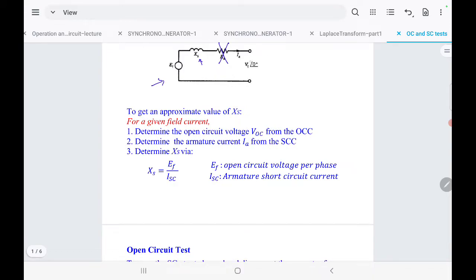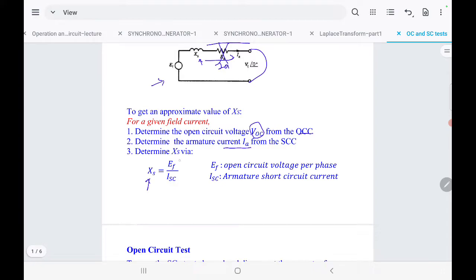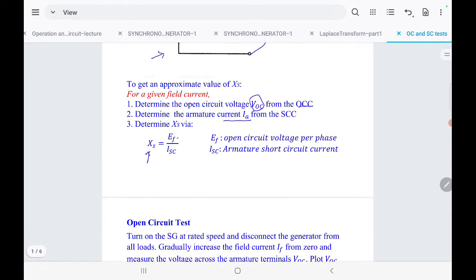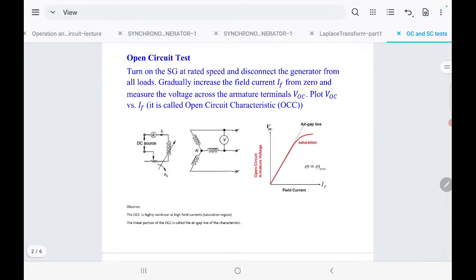To measure XS, we are going to measure the open circuit voltage VOC using the open circuit characteristic, and determine the armature current IA when we have a short circuit. From both values we can calculate the synchronous reactance XS by dividing the open circuit voltage EF by the short circuit current in the armature.